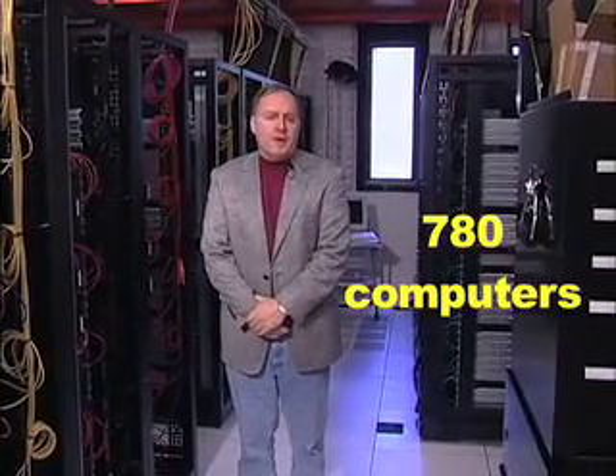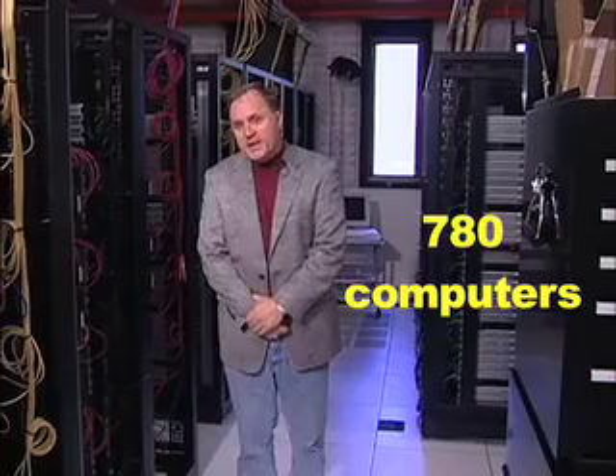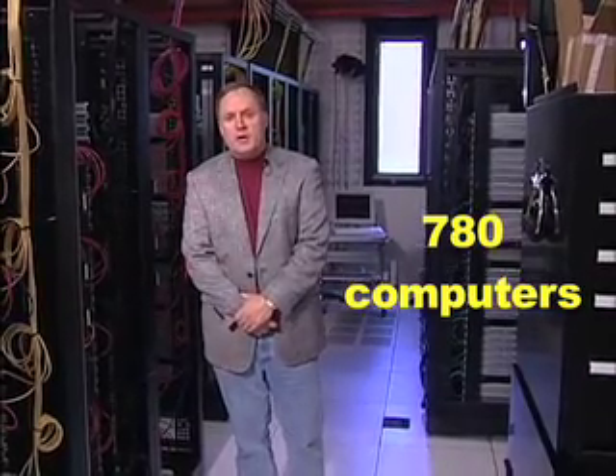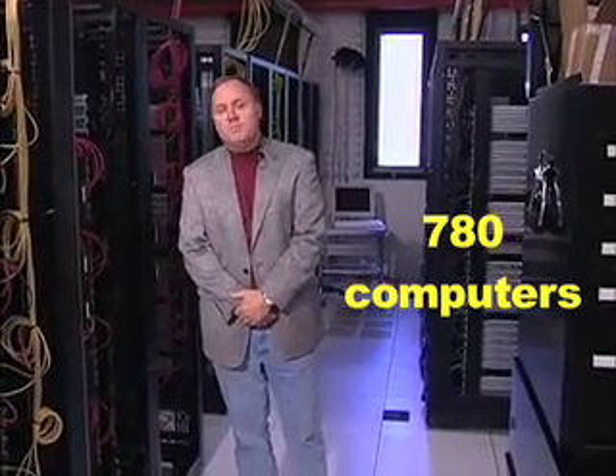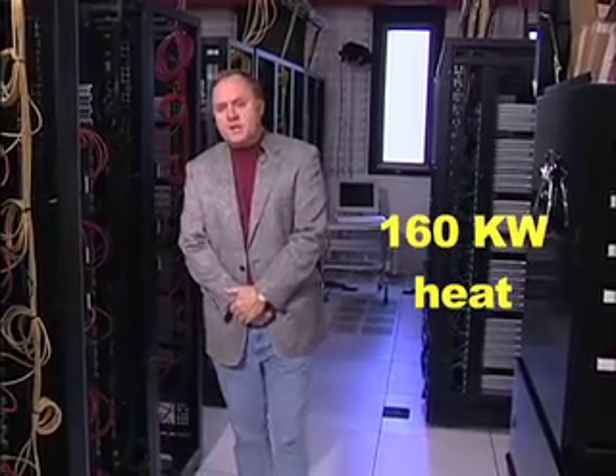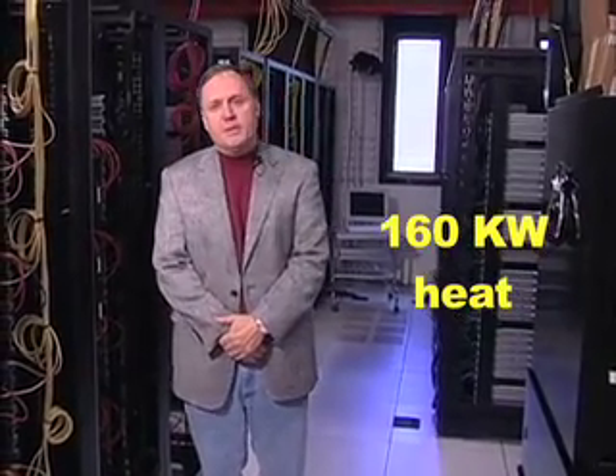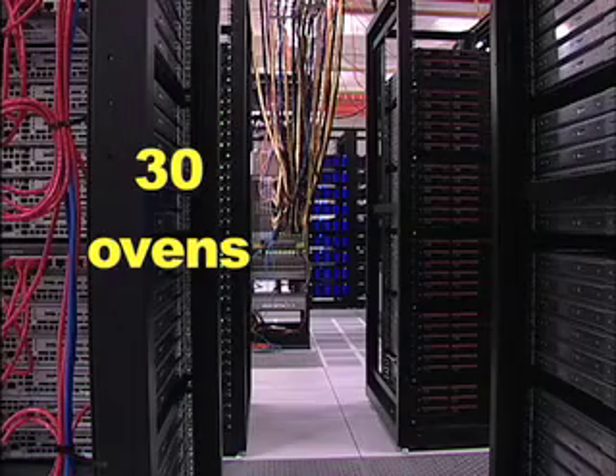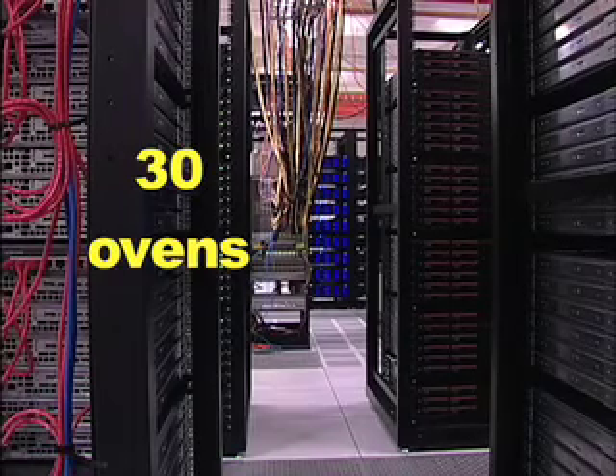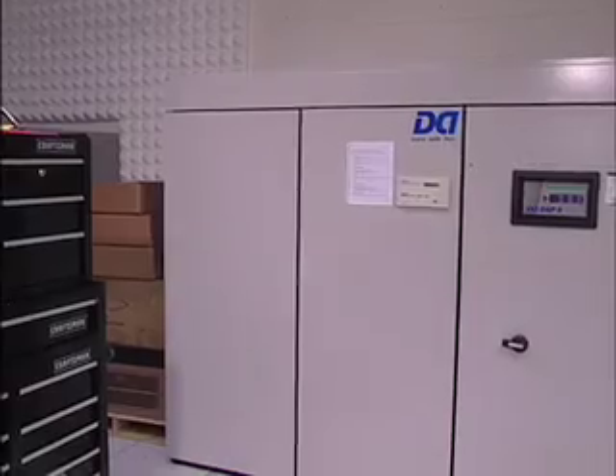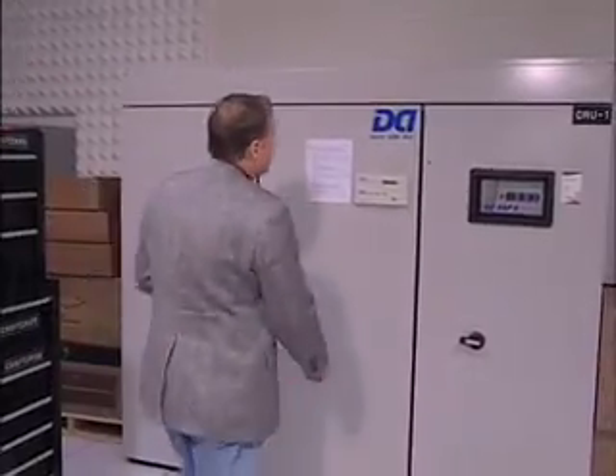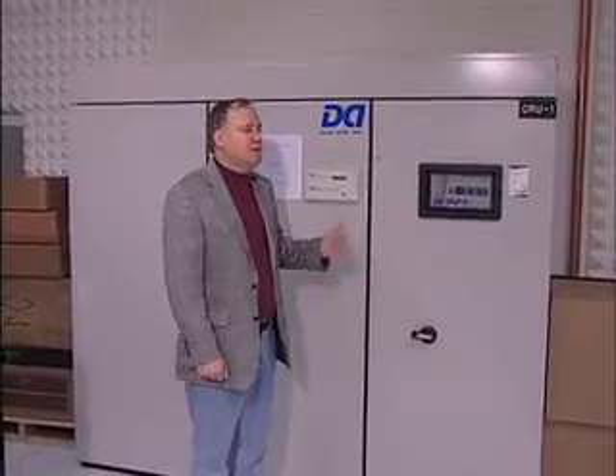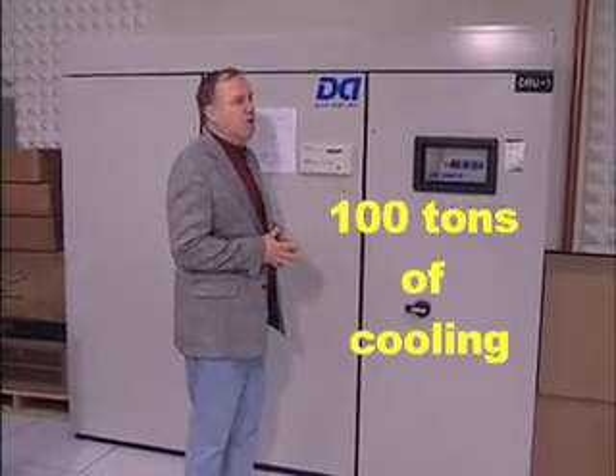As you know from operating your home computer, they all put out heat. Each one puts out about 200 watts, and we have 780 of them. So we have about 160 kilowatts of heat in the room that has to be removed. That's basically equivalent to lighting up 30 pretty good sized ovens in the room. In order to remove the heat, we have 4 air conditioning units in the room. These are what we call 25-ton units, which gives us 100 tons of cooling in the room.